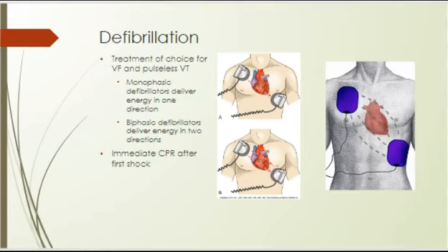You're going to see the AP, for anterior-posterior, patches being applied to the patient, just like you learned in your CPR class. So for those black and white thinkers, yes, we call them AP patches for anterior-posterior, but they are often applied in many different ways, not purely anterior and posterior. The point is to sandwich the heart within them so the electricity flows.